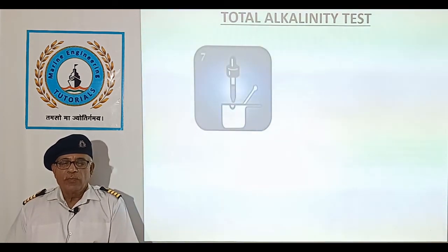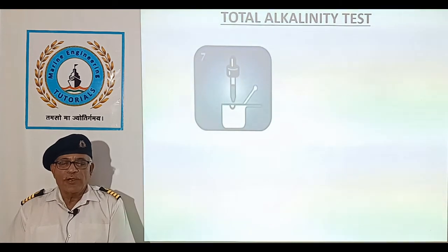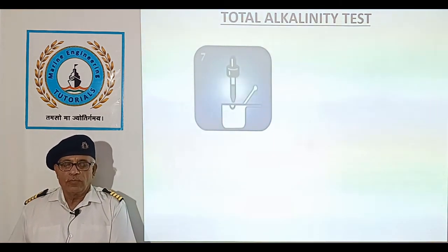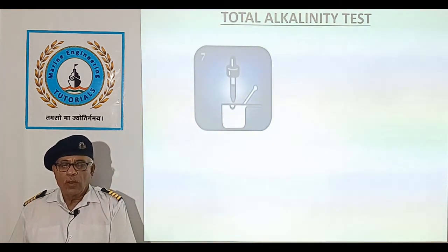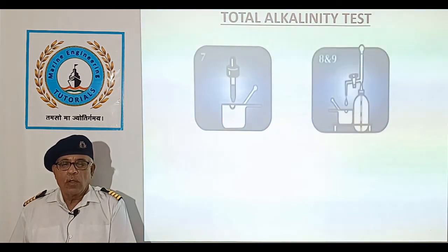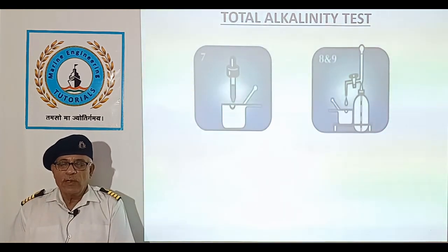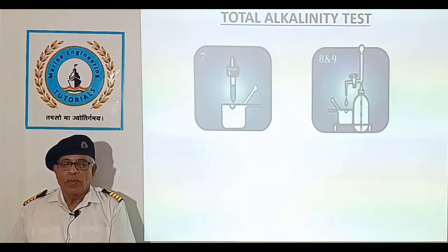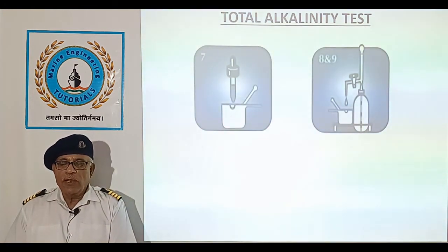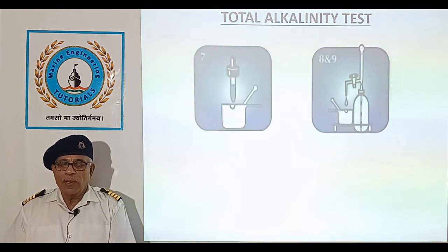Add 3 drops of total alkalinity indicator. Continue the titration and note the final level of acid in the burette. Convert millilitres of sulfuric acid used as per the previous table and record the result in ppm as total alkalinity.